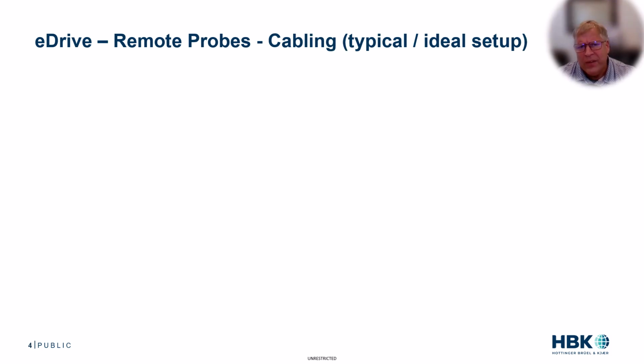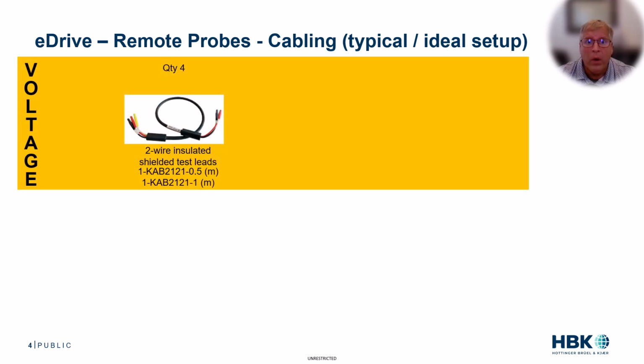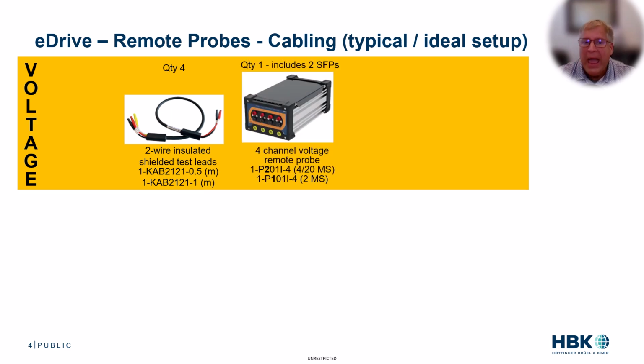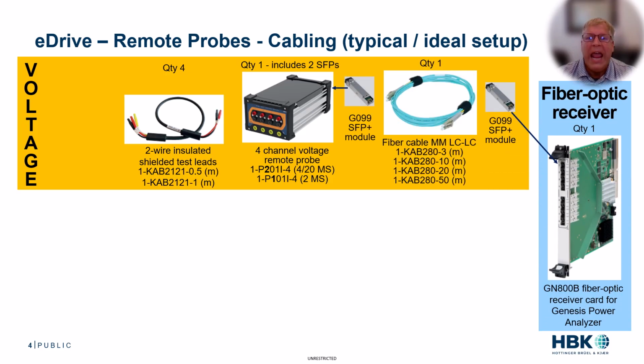Now, a typical ideal remote probe cabling setup would look something like this. For voltage, you can use 4 of the short half or 1 meter 2-wire insulated shielded test leads, KAB2121, to connect the voltage to the 4-channel voltage remote probe input. Then connect the output of the voltage remote probe to the mainframe's first port on the GN800B fiber optic receiver card using a fiber optic cable, KAB280. Now note that each remote probe includes two SFP plus modules, one to be inserted into the rear of the remote probe and one to be inserted into the GN800B fiber optic receiver card.